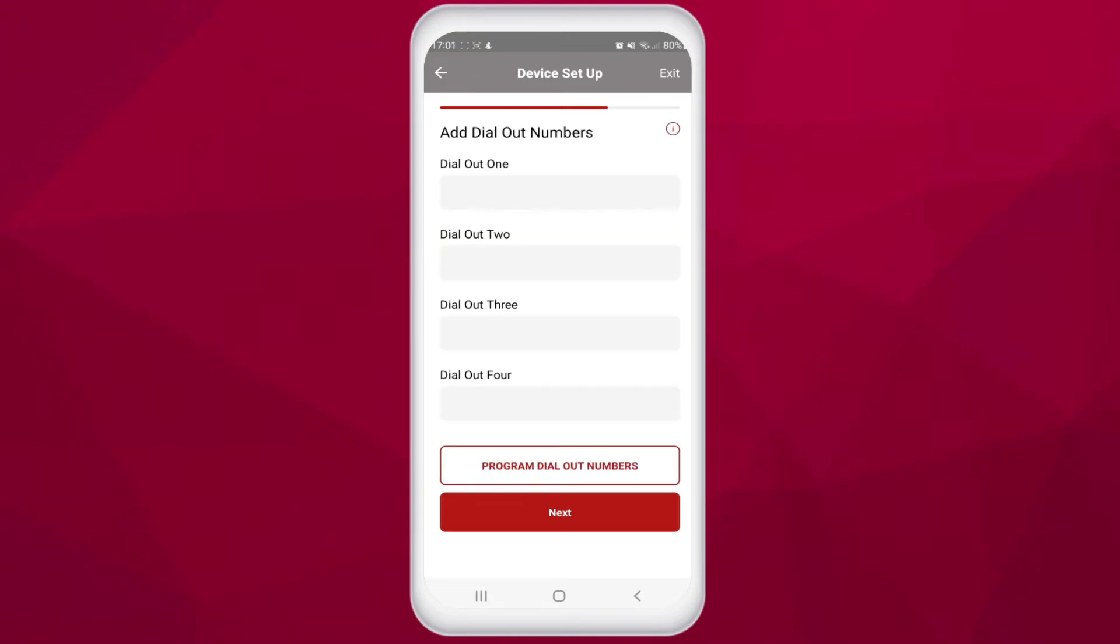Now we can program the dial out numbers. These are the phone numbers the device will call when a visitor presses the call button on the intercom. The unit has a rollover feature so if the first number does not answer, the unit will then try the next number and so on. These dial out numbers are for call button 1 and the rest of the call buttons can be programmed later.